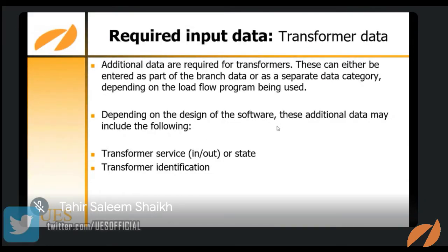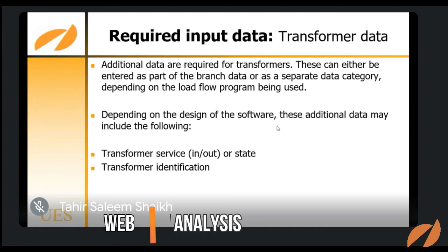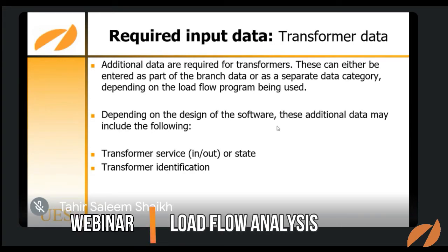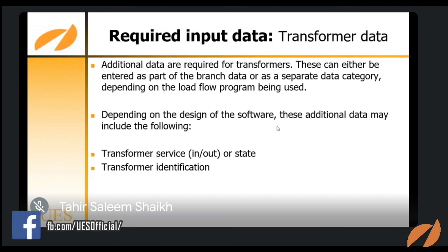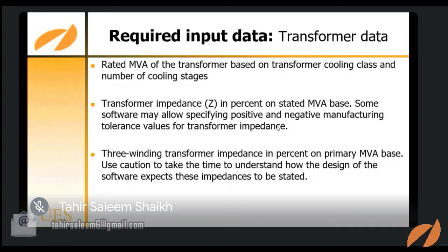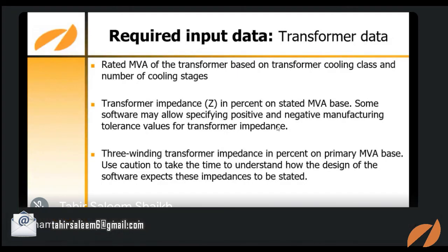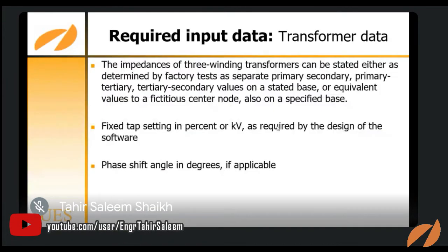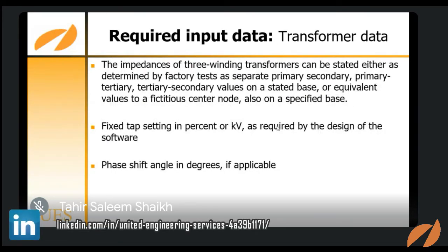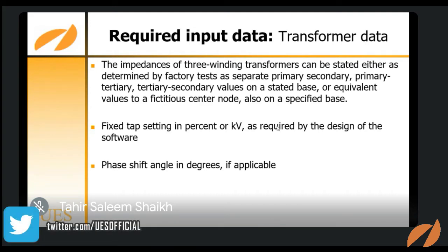Okay, transformer data. A transformer has different data which you are required to insert, like transformer cooling class, transformer altitude, transformer ambient temperature, transformer rated primary and secondary voltage, transformer X by R ratio, transformer impedance, and transformer positive sequence and zero sequence. And then the different statuses, whether the transformer is in service or out of service, transformer identification, the insulation class, and the type of transformer, three winding, two winding or one winding, tap setting, and phase shift in degrees. If you are having this kind of transformer, like a star delta parallel connection, you have to specify these things in the input data.